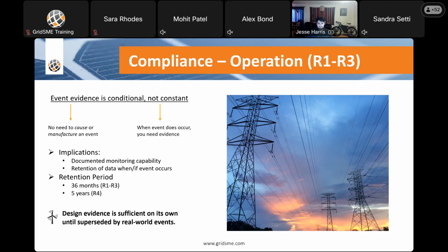Let's talk about compliance for the operation of R1 through R3. Event evidence is conditional, not constant. What this means is there's no need to cause or manufacture an event. But when an event does occur, you need evidence. The implications of this are that you need to have documentation too. Even if you're in a low fault area where you could have an IBR resource that's never experienced a fault in its life, you still need to have documentation that shows that you're capable of monitoring disturbances at the right locations. And also, of course, retention of data when or if that event occurs. The retention period is 36 months for R1 through R3 and then 5 years for R4. Big takeaway from this is that design evidence is sufficient on its own until superseded by real-world events.